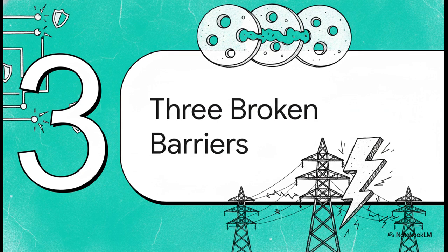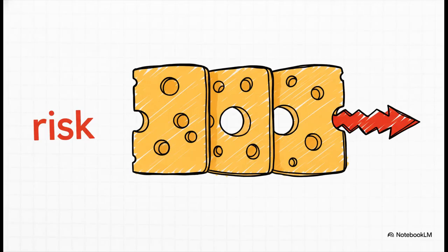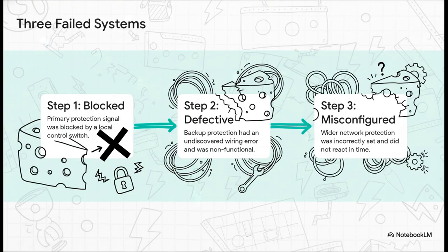So a short circuit happens. This is actually a pretty common event, and there are multiple layers of automated protection designed to stop it instantly. But here, every single one of them failed. To really get our heads around how that's possible, we can use the famous Swiss cheese model of accident causation. The idea is pretty simple, really. Each layer of safety is like a slice of cheese with some holes in it. Normally, if one layer fails, if a risk gets through one of those holes, the next slice of cheese will stop it. A catastrophe only happens on that super rare occasion that all the holes in all the slices just happen to line up perfectly. On September 2nd, they did. We had 3 automated safety systems, 3 slices of cheese, and they all failed, one right after the other.